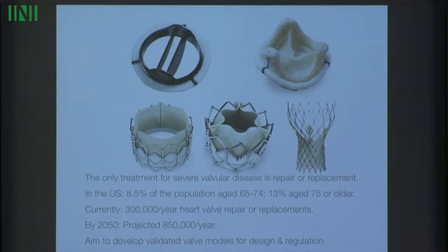The other tissue that's used, especially in more recent devices that allow for transcatheter delivery, are bovine and porcine pericardial tissues. These are examples of valves that are mounted in stents, so you can collapse them down and deploy them using a catheter. One of the advantages of pericardial tissues compared to pig valves is that you can make valves with much thinner materials.